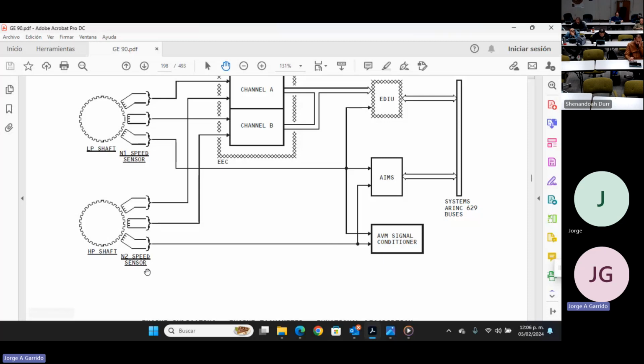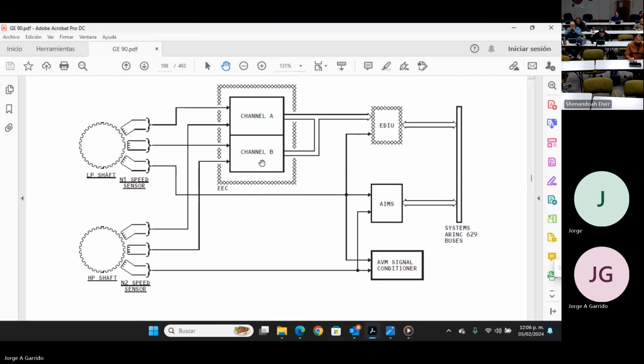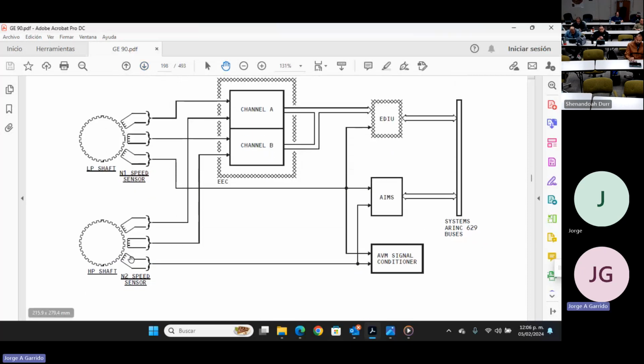Also, as we review the N2 speed sensor signal, 2 of those wires feed channel A and B, and the third one goes to the AVM signal conditioner. If you look at how many connectors and lines are installed in this assembly, you know part of them feed information into the EEC, and both channels need to know what reading is picked up from here. It's very simple, there are always 3 lines going through there, one connector with 3 wires.